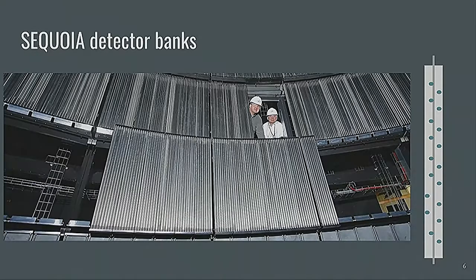You will notice that there are gaps, but these gaps are offset between the layers so that if you, say, fold your detector in half, none of the gaps will overlap. So you have really solid coverage through wide ranges of Q space, your diffracted angles. The really big range is nice because that means you don't lose neutrons even if they're coming off at large angles. So you are getting just more neutrons at your detector.